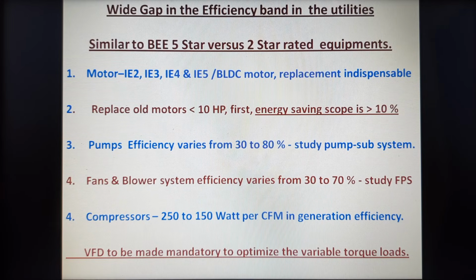All the compressors we are running consume around 250 to 300 watts per CFM, whereas the latest generation energy efficient screw compressors deliver around 150 to 180 watts per CFM only. You can save around 25 to 30% in the compressor itself. So the VFD definitely becomes a mandatory retrofit to variable torque loads like the pumps, compressors or blowers.